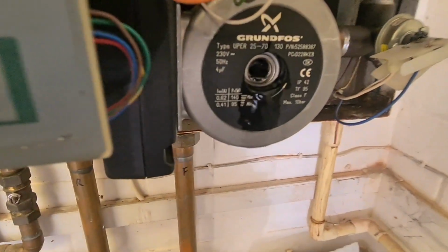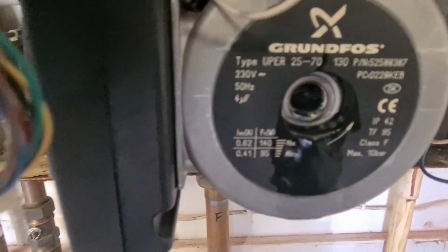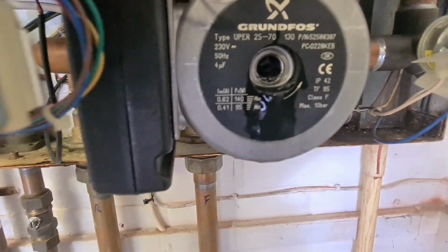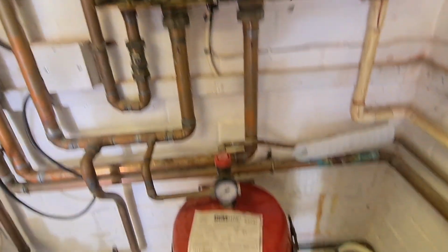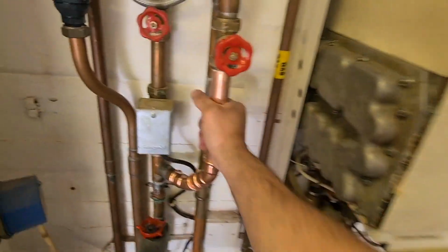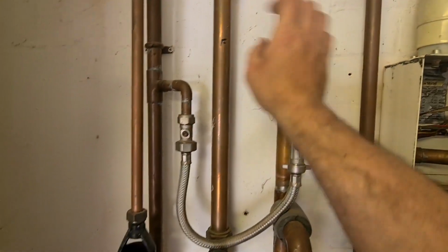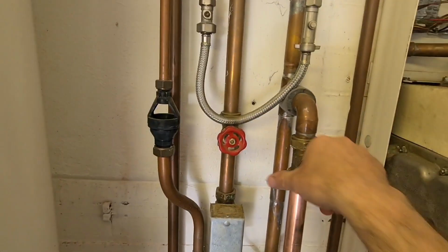So again, as I'm filling, loops open, what I always do, whip the pump head off. You can't see much, but little particles of bubbles are coming out. Again, I'm just bleeding the burner off, the boiler I should say. There is a drain over there, so it's not an issue. But as I get that bled off and start getting this system filled back up, I'll go check all the radiators and stuff soon as well, just to see what's going on.